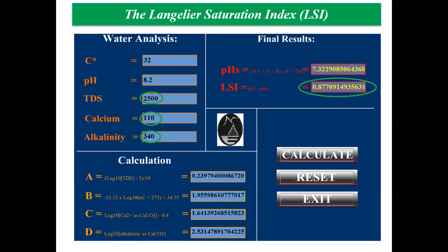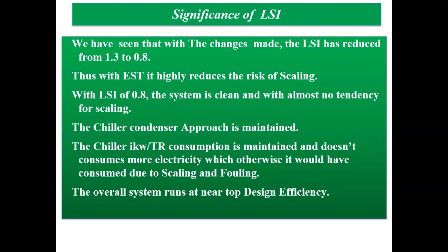So you can see it has drastically reduced from 1.3 to 0.8. That is a clear indication that the water is now less prone to scaling, and whatever scaling will be there will be taken care of by the EST system. So here is a detailed view: the LSI dropped from 1.3 to 0.8. The system is cleaner and has nearly no tendency for scaling. Based on that, your chiller approach will be maintained, and IKW per TR consumption will be maintained, and the overall system will likely run at design efficiency.